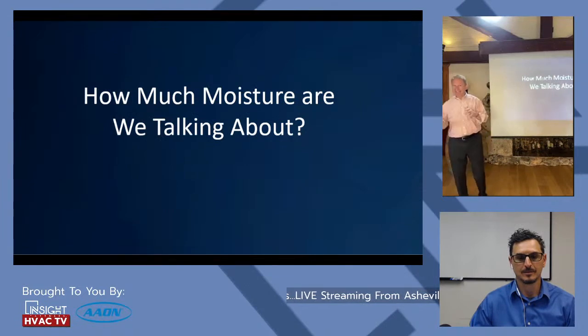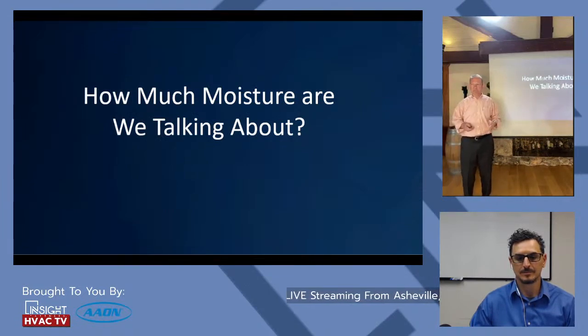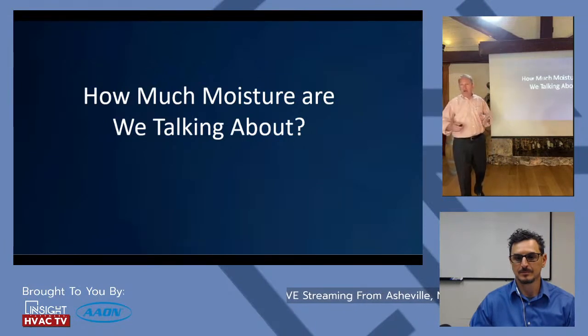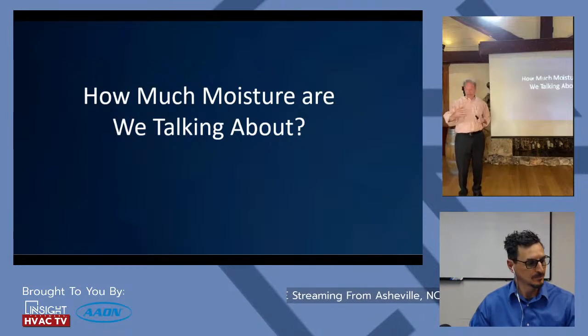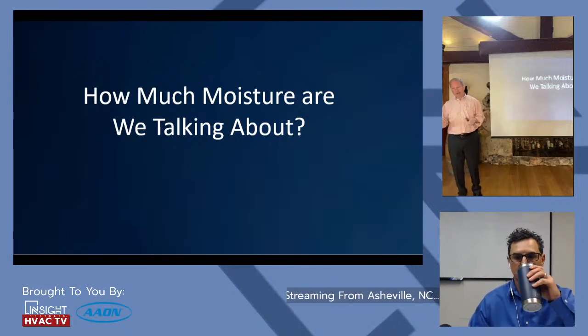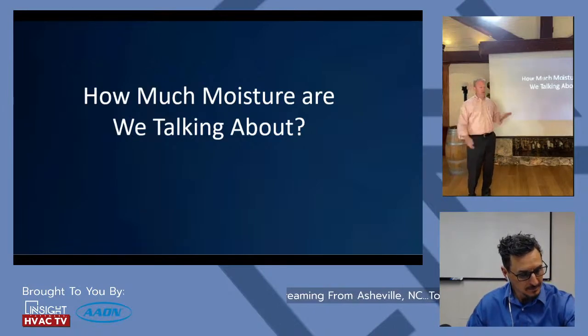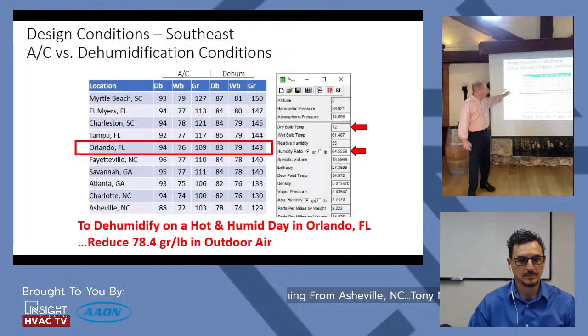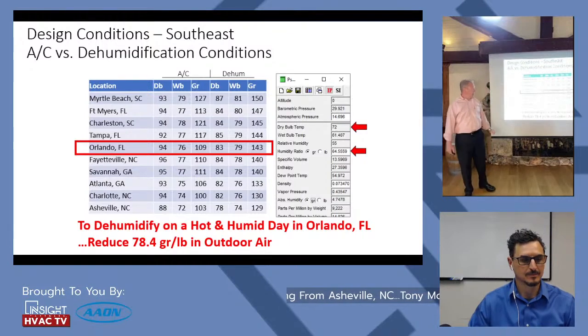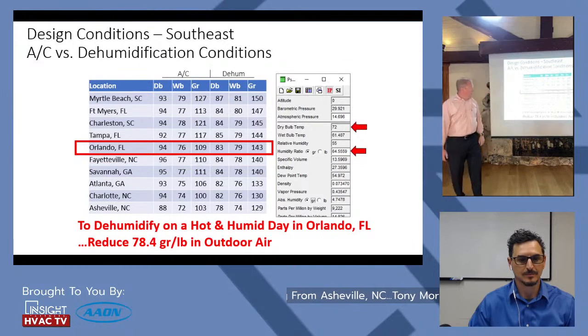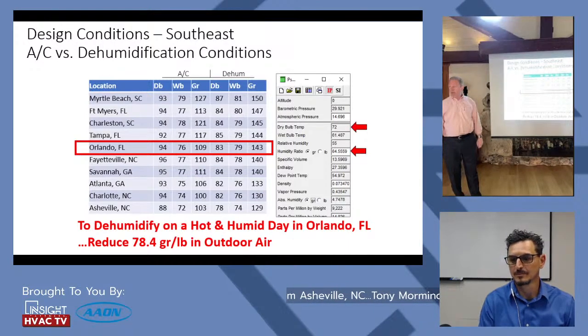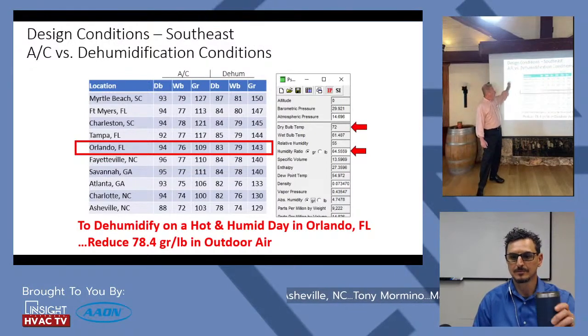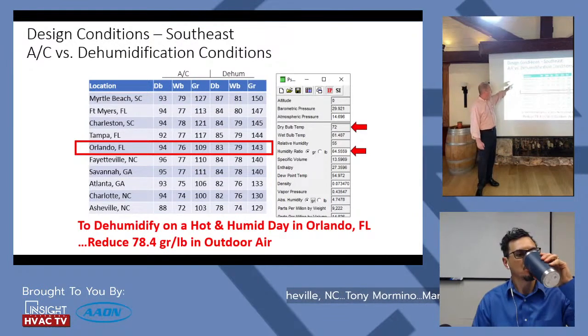How much moisture are we actually dealing with in DX systems? A typical DX system has some return air and some outside air in most commercial applications. In Orlando, the air conditioning design condition is 94°F dry bulb at 76°F wet bulb — 109 grains. But the dehumidification design condition is 83°F at 143 grains. Myrtle Beach, South Carolina actually has the highest grain loading, beating out Fort Myers, Tampa, and Orlando.